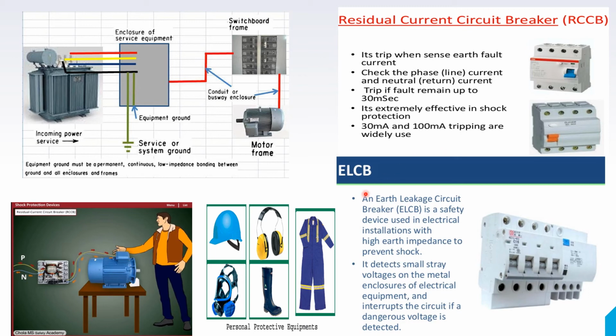The next device which is used is the ELCB, that is Earth Leakage Circuit Breaker. It is a safety device used in electrical installations with high earth impedance to prevent shock. It detects small stray voltages on the metal enclosures of electrical equipment and interrupts the circuit if dangerous voltage is detected. So this is the ELCB. Here we can see personal protective equipment like gloves, cap and suit.